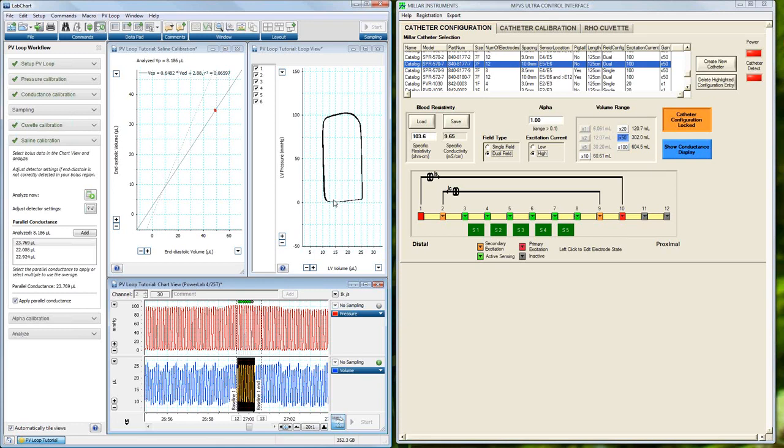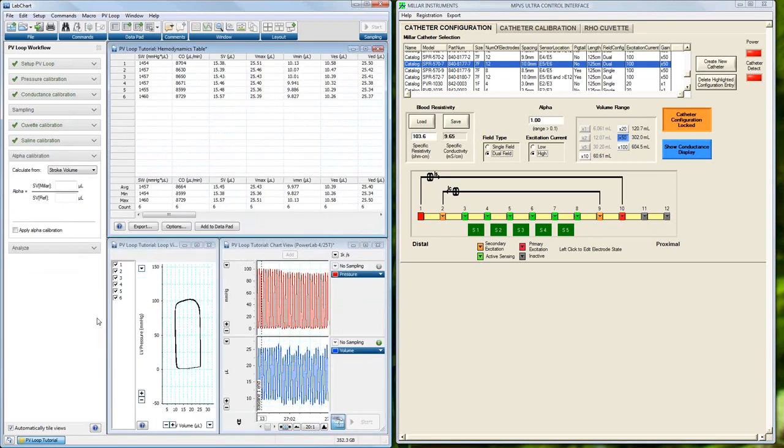And this is where we can actually take our echo data and say we figure out stroke volume from some sort of reference, echo, some other method that you're going to find out to actually calculate a reference stroke volume. We look at our stroke volume for the Millar catheter. We can also use cardiac output if we'd like. And it gives us a correction factor against a known good standard to take care of any variation at all.